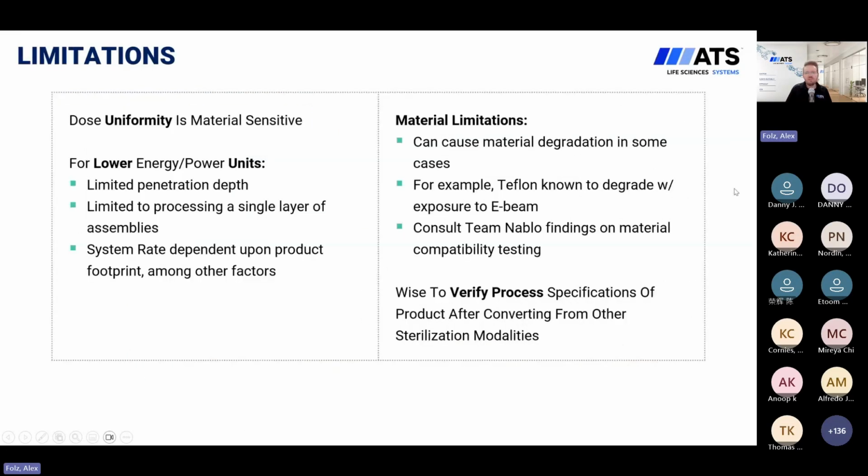So, looking at the other side, there are also limitations to E-beam, right? There's usually pros and cons to every modality, and E-beam is no different. So some limitations here that we're looking at is, first and foremost, dose uniformity is going to be very material sensitive. In addition to that, particularly for lower energy and power units, there's limited penetration depth. We're typically limited to processing a single layer of assemblies.